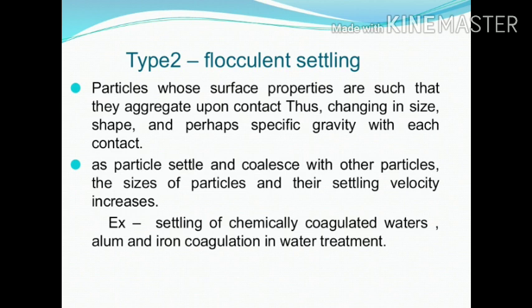Type 2 is flocculant settling. Here, flocculation of particles occurs, increasing their mass, so they settle at a faster rate. The particles are in contact with each other, changing in size, shape, and specific gravity. As particles settle with other particles, their size and settling velocity are affected. An example is settling of chemically coagulated waters — such as alum and iron coagulation in water treatment.